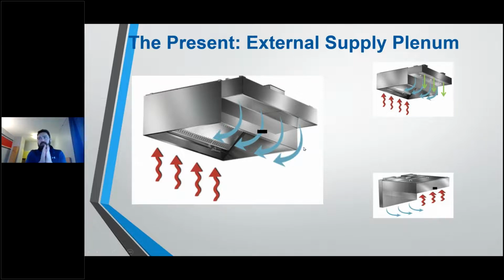So you're going to bring it down right at the face of the hood. It's going to create what's called an air curtain. And now most of that air, I don't know the percentage, but a high percentage of that air is going to naturally shift back into the exhaust hood, and it's going to be exhausted right away. So that way we don't have to fully temper this air. So it's a better decision, not only upfront cost for the client, but also ongoing energy efficiency of not dehumidifying this air. I call it cutting the air, just bringing it down to within 10 degrees of ambient and then exhausting most of it. And then what does roll out the front of this curtain is going to be picked up by your rooftop units, keeping in mind that kitchens are energy hogs, and they're naturally humid. They are. Again, when I was a cook, it's not comfortable.